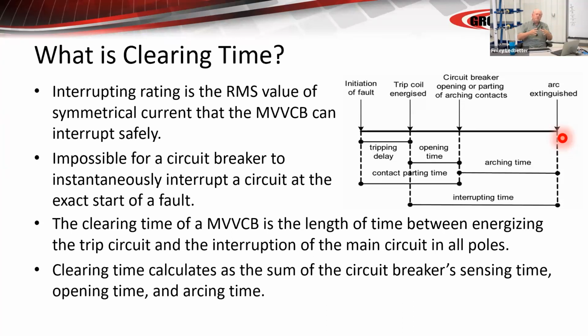So if a 30 or 40 millisecond breaker is pushed out to 100, like it would be with a long setting inactive for many years, now you've doubled the arc flash boundary. And I'm pretty sure that the standards now say you will, not that you might, verify that, and you have to comply with that.